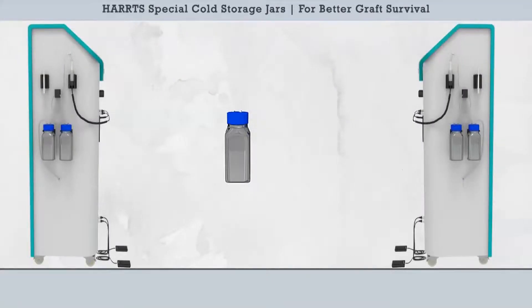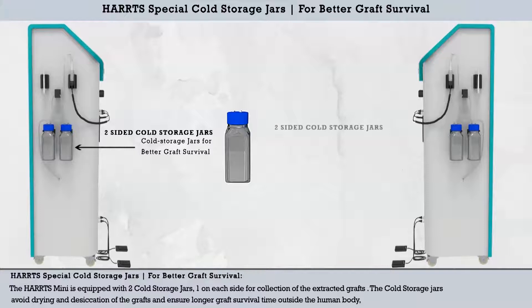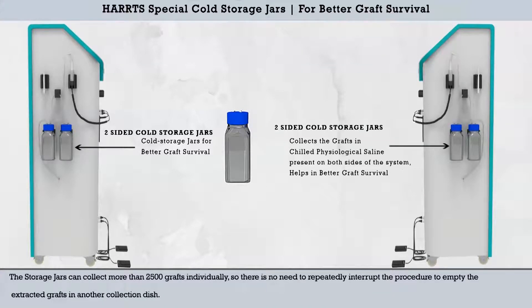The HARRTS Special Cold Storage Jars for Better Graft Survival. The HARRTS Mini is equipped with two cold storage jars, one on each side, for collection of the extracted grafts. The cold storage jars avoid drying and desiccation of the grafts and ensure longer graft survival time outside the human body. Each storage jar can collect more than 2,500 grafts individually, so there is no need to repeatedly interrupt the procedure to empty the extracted grafts into another collection dish.